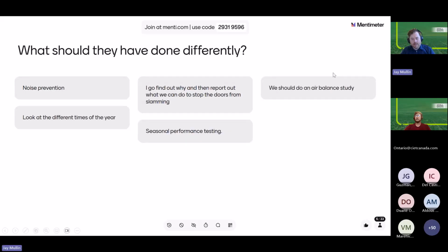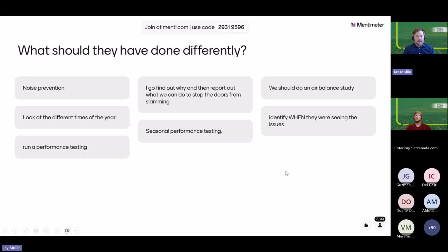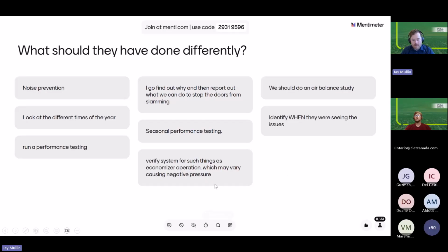Yeah, look at different times of the year, seasonal performance testing. They could have done some testing, setting the conditions of the system to what it is at different seasons. So if their dampers or their outdoor air percentage change throughout the year, do some tests around that. Good point about identifying when they were seeing the issues, really taking that into account and not assuming that they were consistent, that they might be time dependent. Yeah, verifying system things such as economizer operation might be excellent. All right, so these are all great tips on how they could have avoided that challenge.